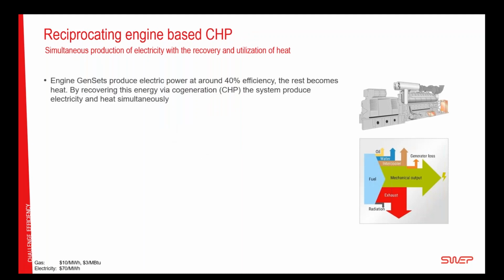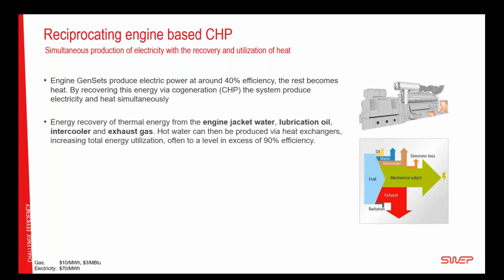An engine genset is a large engine that consumes fuel, which could be gas or diesel or even petrol, to create electric energy. And that is about 40% of all the energy that you put in that you get out as electricity. And it's not bad, but if you start to recover energy from the jacket water, from the intercooler, from the oil, and from the exhaust gas, you will be able to use 90% of the total energy that you put in.